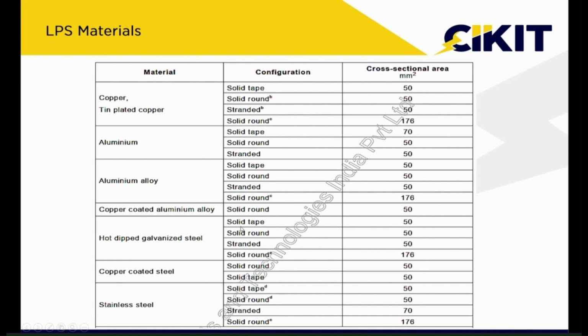And if you observe it clearly, for the copper itself, solid tape is nothing but strip configuration. Solid round is nothing but rod configuration. The stranded is nothing but similar to the cable. And the fourth one is also round. Here the difference is the first three are for down conductors, whereas the fourth one is for air terminal. So we know that if a lightning impulse current is flowing through the air terminal, it will be having a minimum of two parallel paths from the air terminal to the ground. So the current flowing through any down conductor will always be lesser than the current flowing through the air terminal. That is the reason the air terminal will always be bigger in size than the down conductors. So as per the standard recommendation, we have to go for 176 square mm for air terminals and a minimum of 50 square mm for the down conductors.